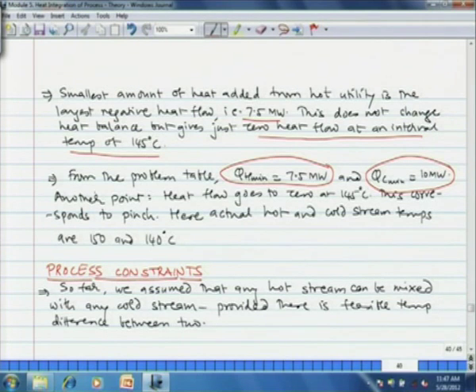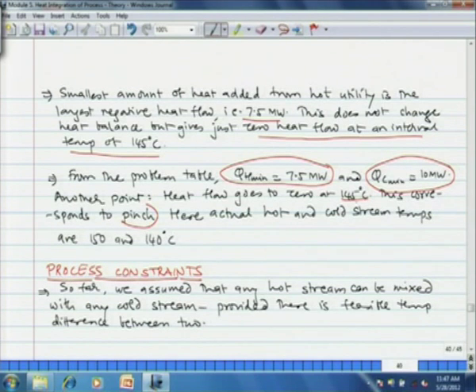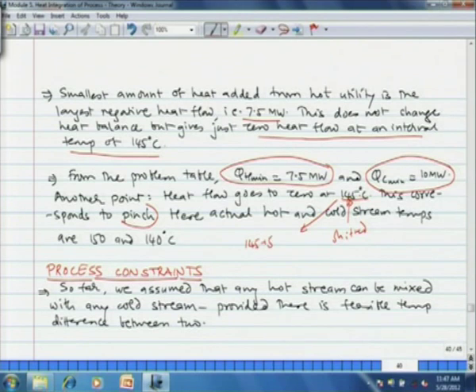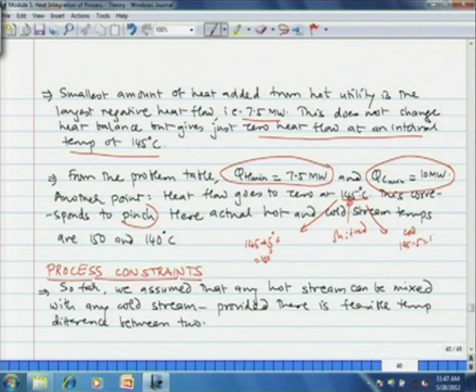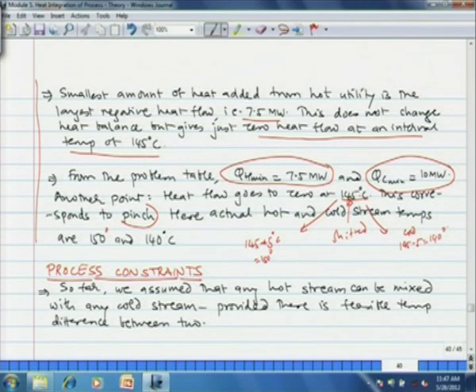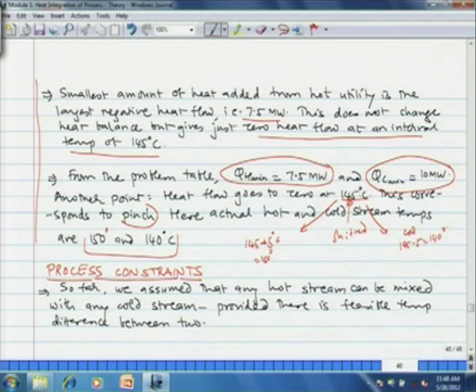The heat flow goes to 0 at 145°C, which corresponds to the pinch. But remember, 145°C is the shifted temperature interval. For this temperature, the hot streams are at 145 + 5 = 150°C and the cold streams are at 145 − 5 = 140°C. So the actual hot and cold stream pinch temperatures are 150°C and 140°C respectively. We have thus determined the minimum hot and cold utility requirement and the pinch temperatures without plotting a graph.